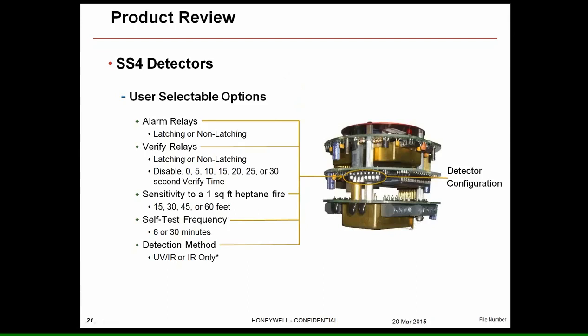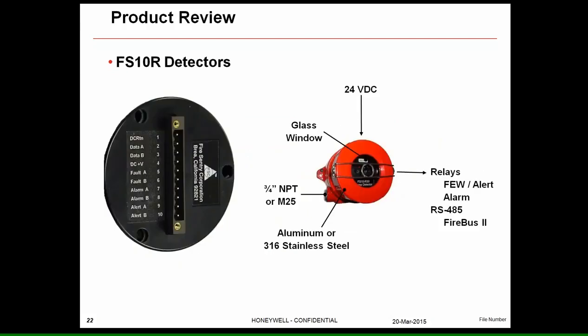Going back to the previous slide — this brass box held on by a clip and screw actually pulls out of the board set. That is where the source lamp is located, running through a brass tube into a darker tube. You can undo the clip and pull the whole source lamp assembly out and replace it. Recognizing that the source lamp lasts five or six years, it's an item you can stock on the shelf.